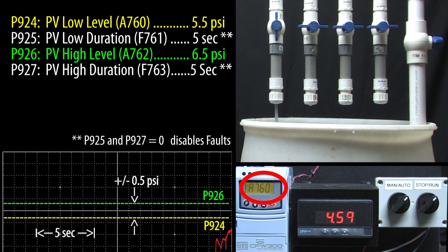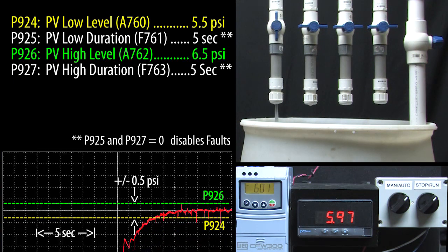And we immediately see an alarm telling us there is a low pressure. That's okay, we are ramping up. Again, if that ramp took longer than 5 seconds, the drive would issue a fault and shut down. This process ramped up in less than 5 seconds so we are in good shape and the alarm went away. Perfect.